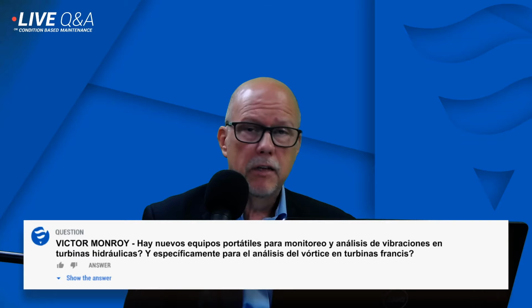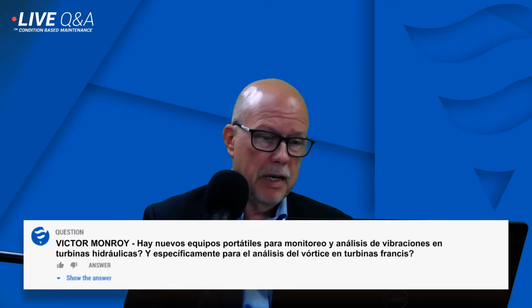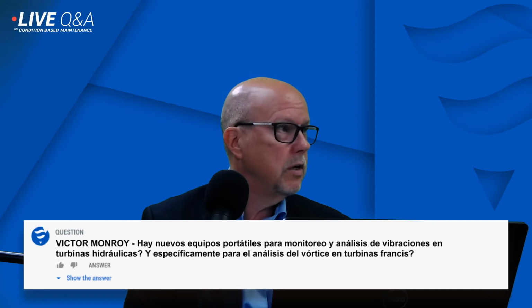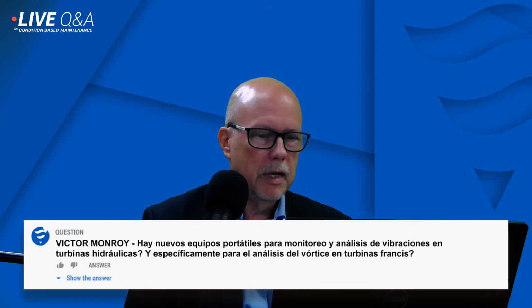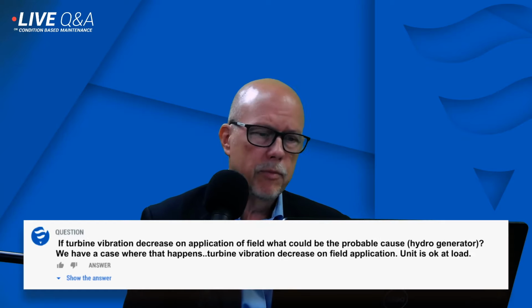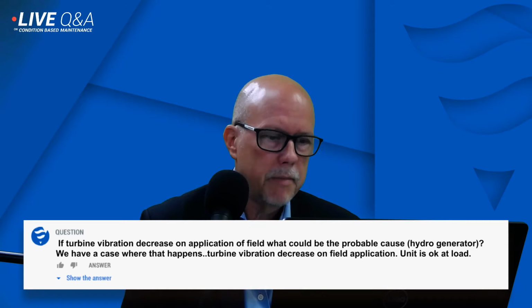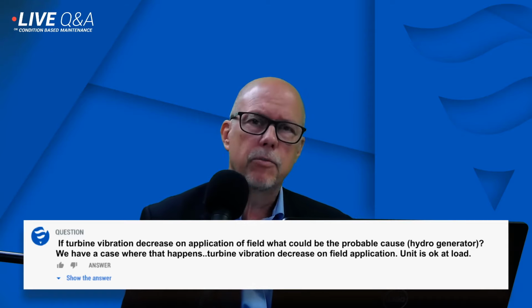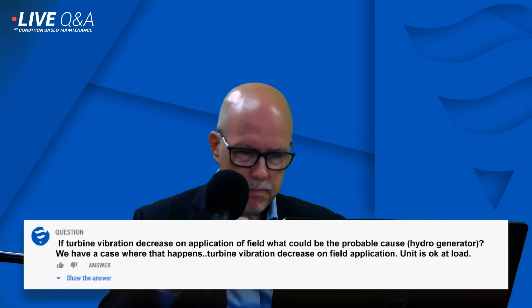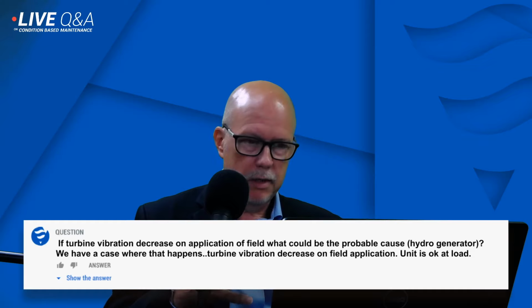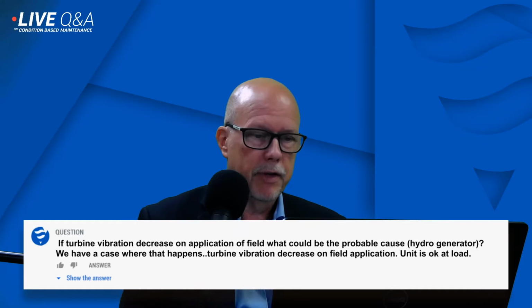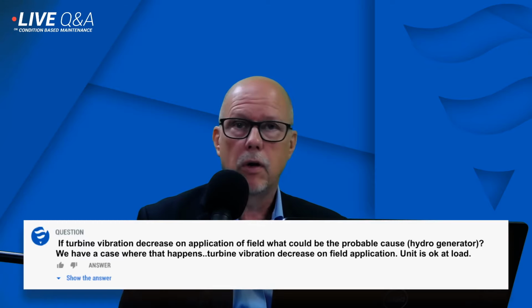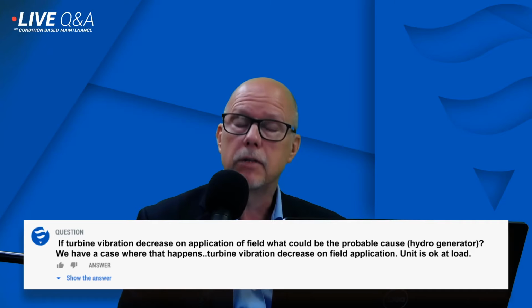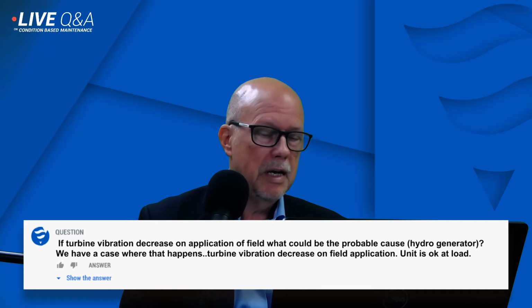Well, it doesn't give me a lot of information. I have questions. If Mr. Dhirendra is online or would like to join us at some time, I would ask him if the vibration at the turbine decreases, what happens to the vibration at the other bearings? Does it also decrease? I mean, when you apply the field, you expect to see the vibration decrease because the rotor and the stator become magnetically coupled, and that usually settles the unit down significantly. So if you have that situation where the overall vibration of the unit decreases, I would expect to see the vibration at the turbine decrease as well.